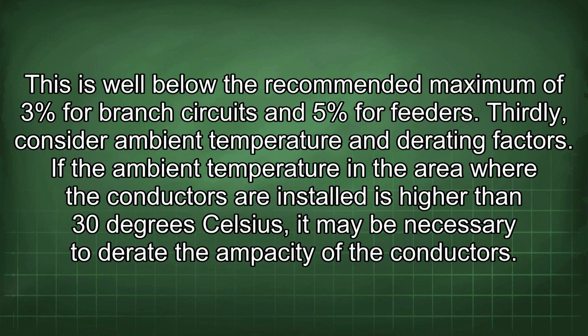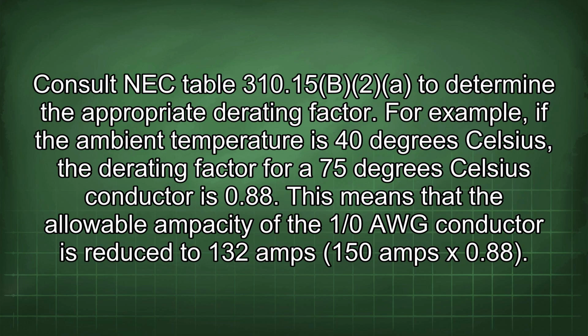Thirdly, consider ambient temperature and derating factors. If the ambient temperature in the area where the conductors are installed is higher than 30 degrees Celsius, it may be necessary to derate the ampacity of the conductors. Consult NEC Table 310.15(B)(2) to determine the appropriate derating factor.